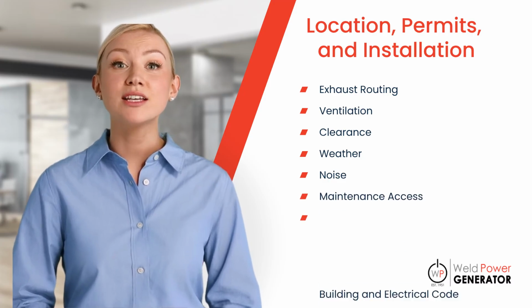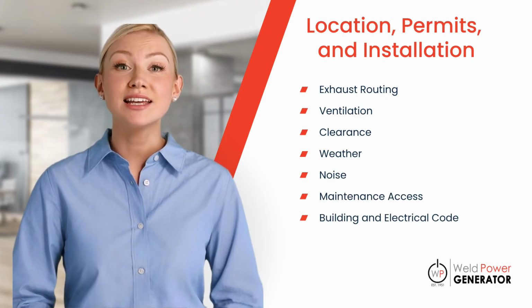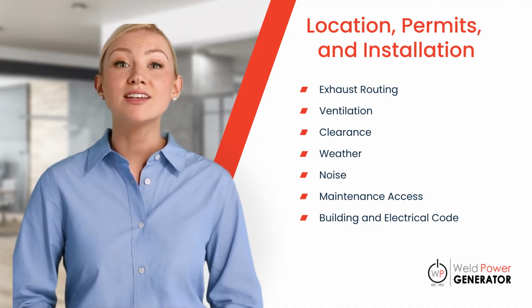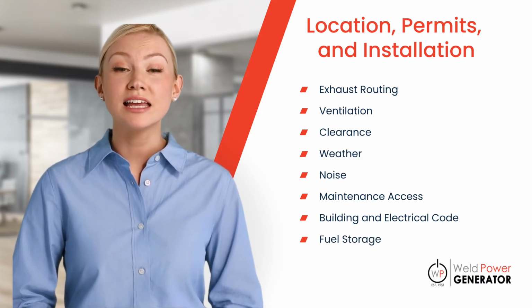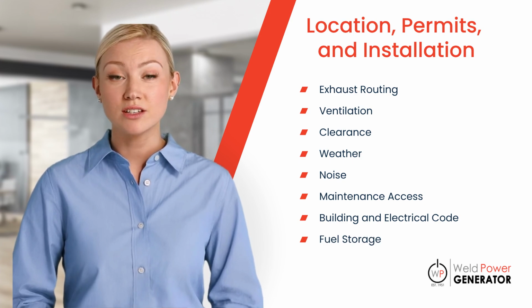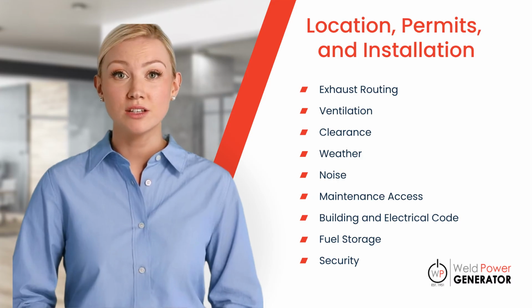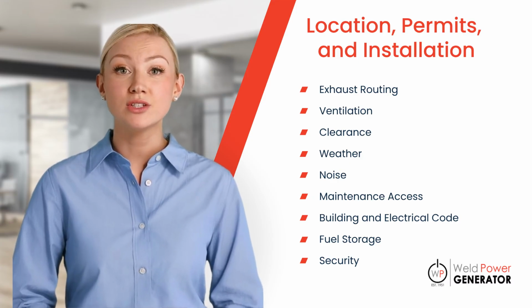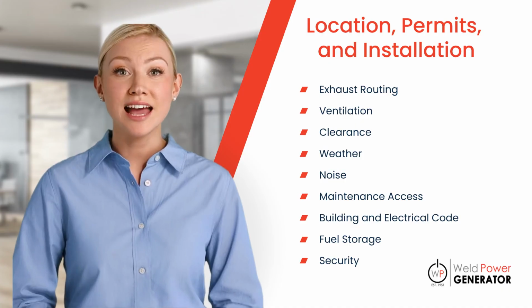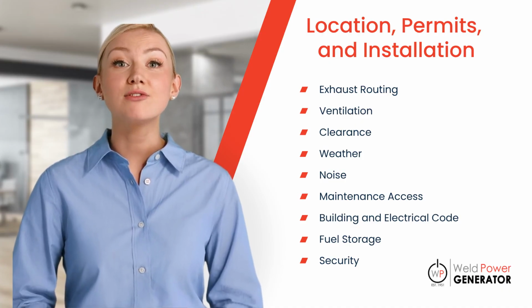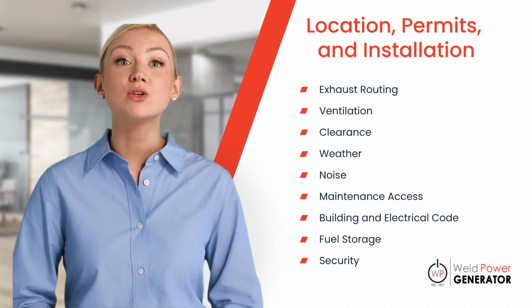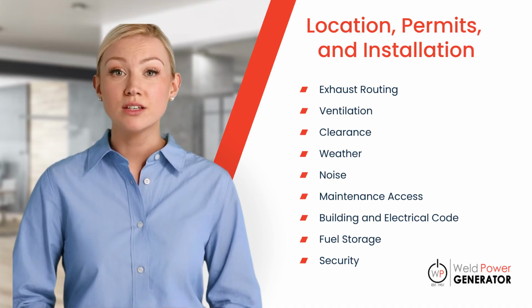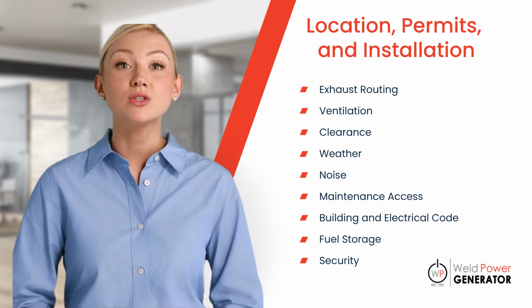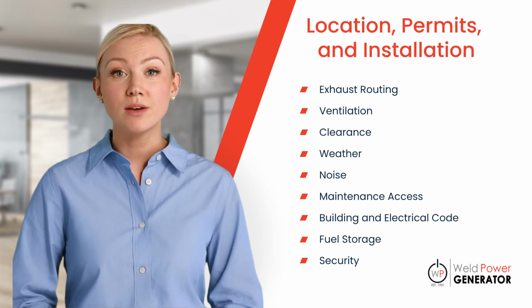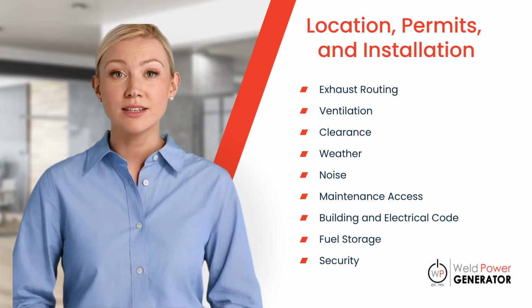Building codes, electrical codes, environmental regulations, and permitting requirements will heavily influence your generator placement. Fuel storage must also meet code requirements for containment, access, and distance from structures. Security is another major consideration. The unit should be accessible for routine service, but protected from unauthorized access or vandalism. Even if you're replacing an existing generator, don't assume the old location still meets current codes. Updates to building and electrical codes or changes to your building's infrastructure may not allow a direct replacement.